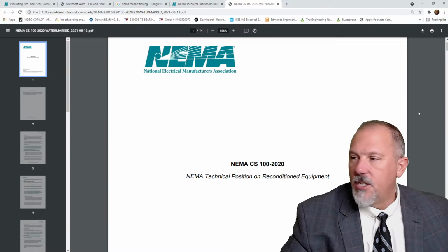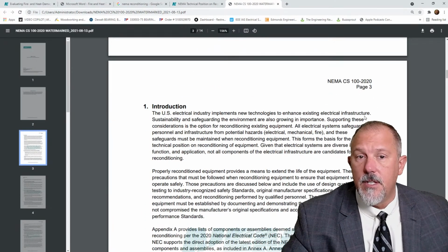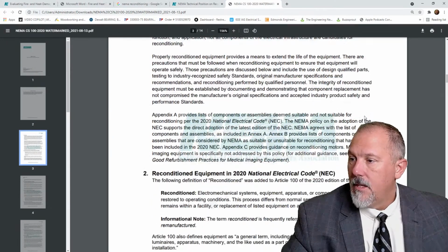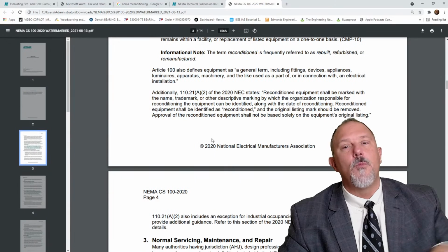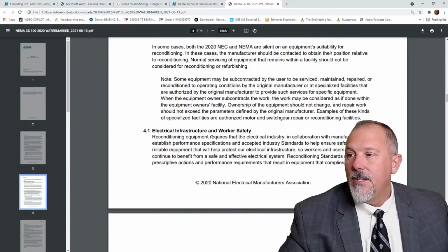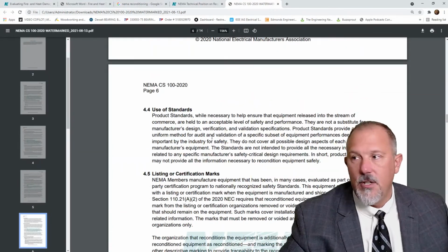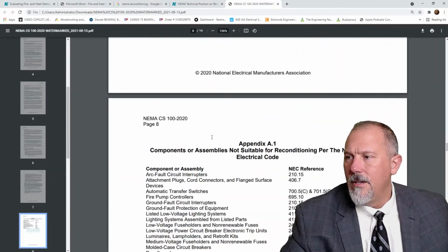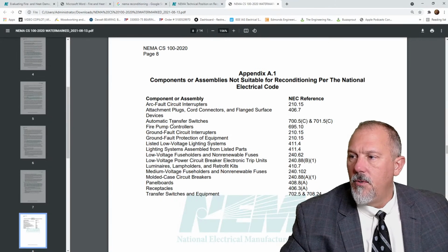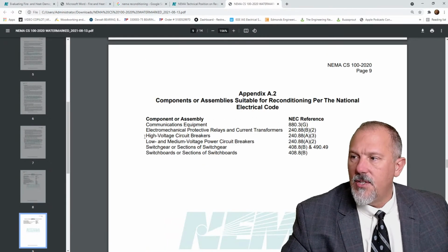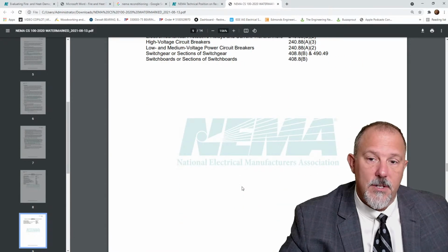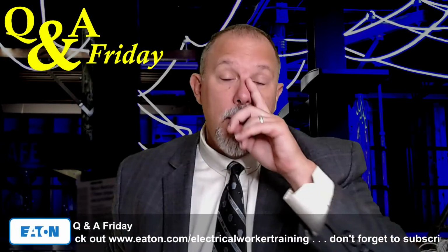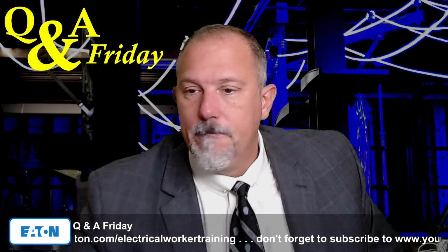NEMA technical position on reconditioned equipment. This is what I was looking at. So this is another reference to answer this one. You'll see what is reconditioned, and this is in alignment with the National Electrical Code. So I'm just perusing through there. This is a free document. You can get it off of their website. I'm just looking for, there it is, components or assemblies not suitable for reconditioning per the National Electrical Code. You've got panelboards, receptacles, low voltage lighting, etc. So I would leverage this in your discussion, and this is a nice document because it gets you to all of the areas where you can and cannot recondition equipment.